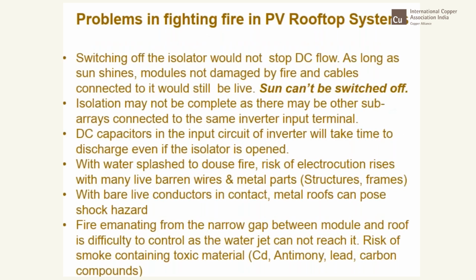The problem in firefighting, particularly fighting a PV fire, is that switching off the isolator would not stop DC flow, especially during daytime. Of course, at nighttime there is no possibility of fire because there is no generation. But when you think you have switched off, or removed certain cables, as long as the sunlight is there and the solar cell is physically all right, it will generate electricity, and many of the cables will be live. More so if the insulation has been stripped because of heat, then you will have live wire spread across the roof.